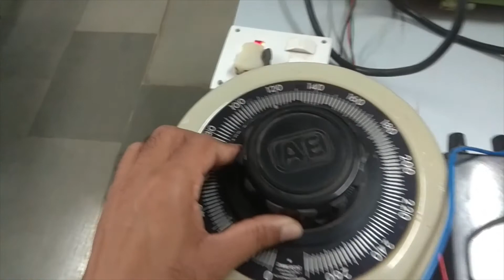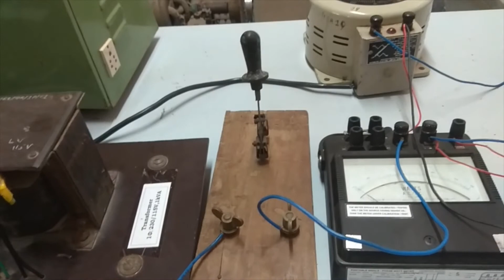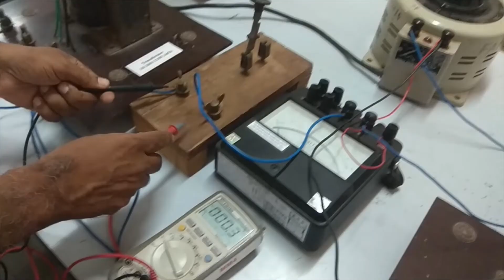After that, we will check whether the secondaries of the transformers are connected in series with reverse polarity or not. That can be seen by measuring the voltage across these two terminals, and it should read 0. If it is reading 0, it says that the secondaries are connected in series with reverse polarity. So let's check that. Now we have connected a voltmeter across this, and we can see that the reading is 0 volt. It means that the secondaries are connected in series with reverse polarity.